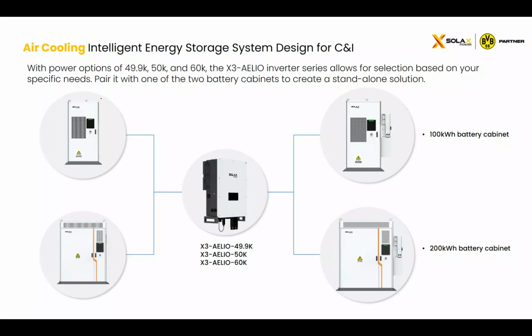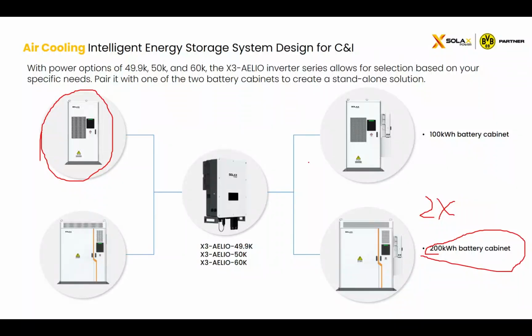Okay, and let's go on. Since AELIO has two separate battery ports, we offer our customers a variety of battery solutions ranging from 100 kilowatt hours to 400 kilowatt hours. 100 kilowatt hours means using just the 100 kilowatt hour battery cabinet, and 400 kilowatt hours means it can use two 200 kilowatt hour battery cabinets to form a 400 kilowatt hour whole system capacity. You can combine the AELIO directly with two battery cabinets of any capacity to form a standalone solution. The two battery ports do not need to be connected to the same number of batteries, so for the AELIO, a 300 configuration is also okay.